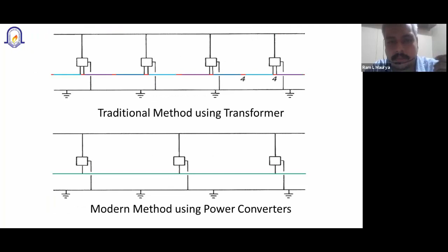In this converter based traction substation, there is a three-phase overhead line, then a step down transformer, and an AC to DC, DC to AC converter. That means a three-phase to single-phase converter. Here you do not have neutral sections. Because you are drawing power from all three phases, there is no unbalance and no harmonics. All these things are solved by this power electronic converter.